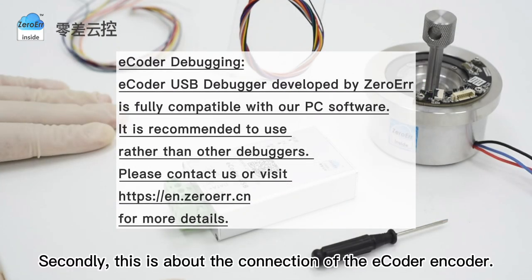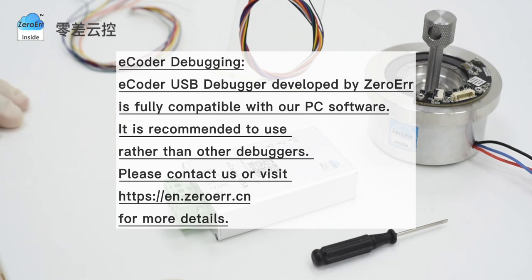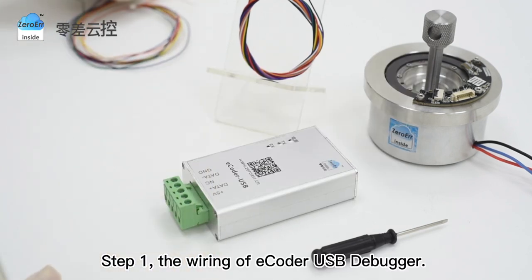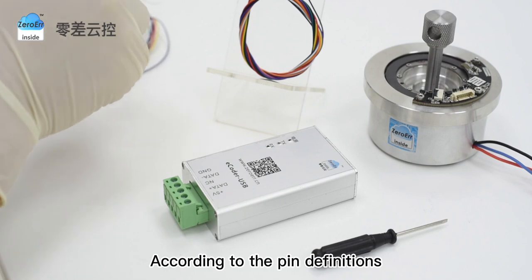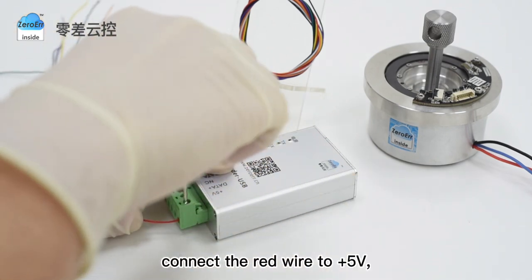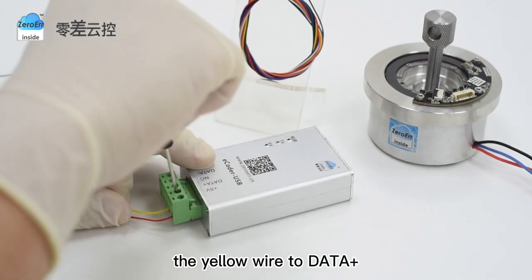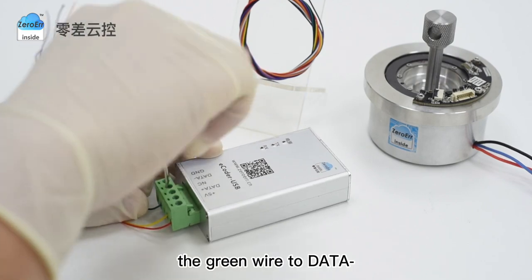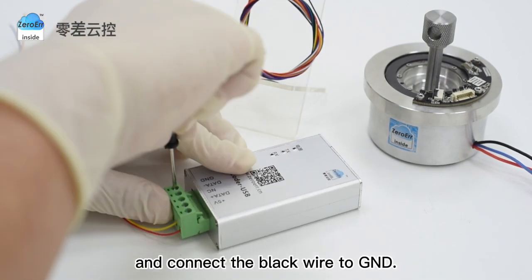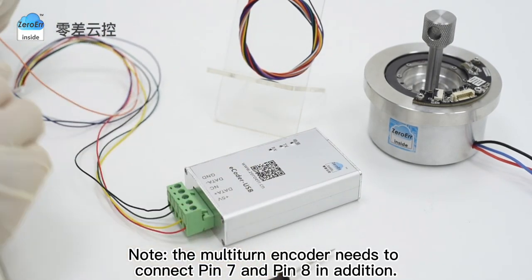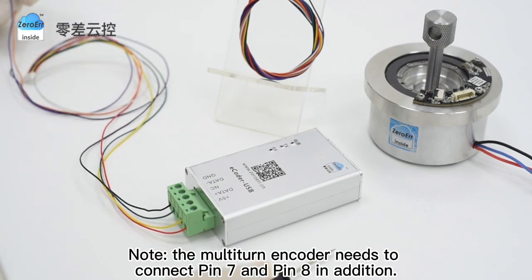Secondly, this is about the connection of the eCoder encoder. Step 1, the wiring of eCoder USB debugger. According to the pin definitions, connect the red wire to positive 5-volt pin, the yellow wire to data plus pin, the green wire to data minus pin, and connect the black wire to ground pin. Note the multi-turn encoder needs to connect pin 7 and pin 8 in addition.